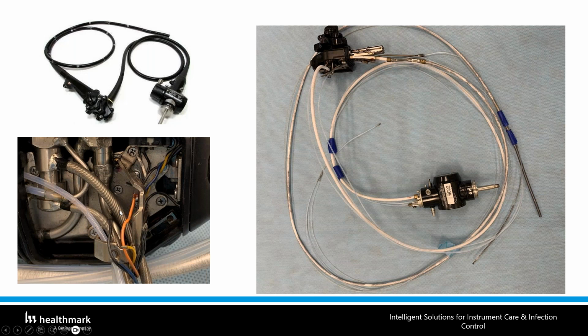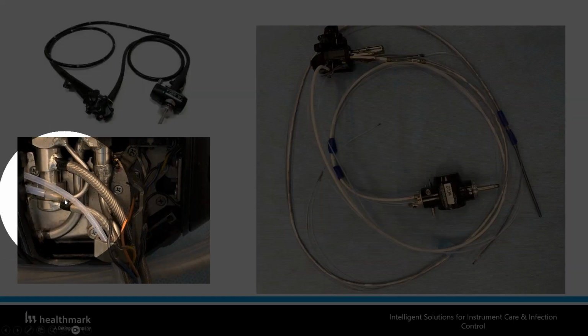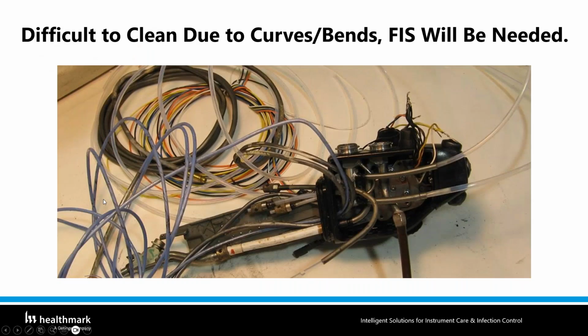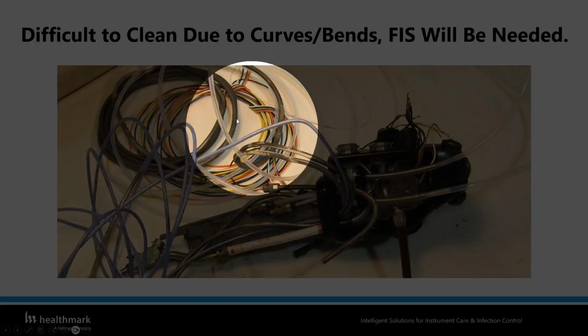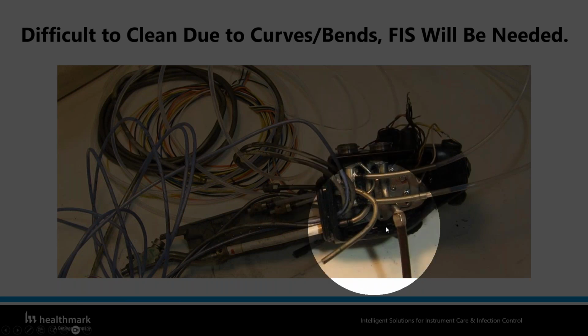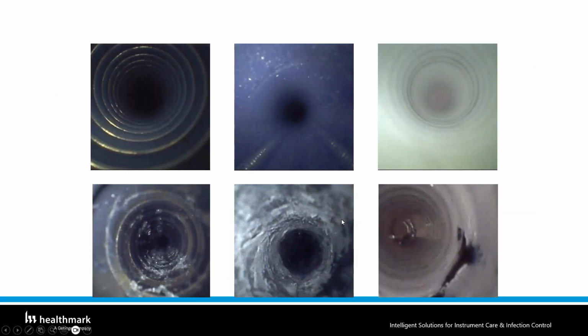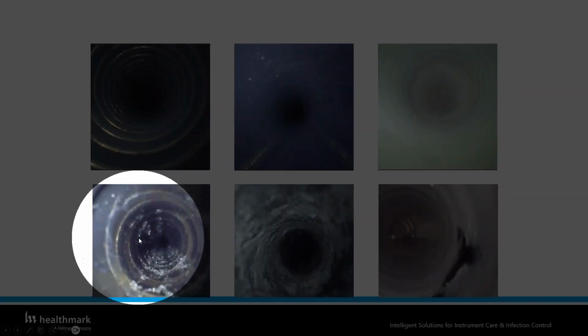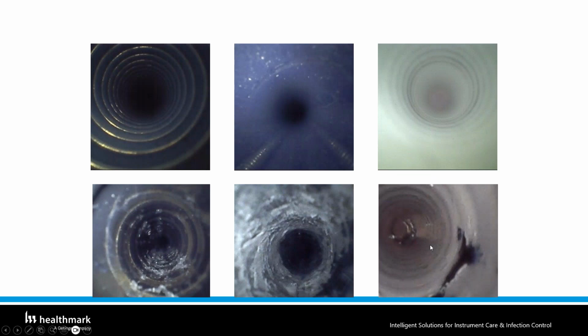So it's a nice technology, versus having to do open surgery to look inside. This does help a lot. But as you see, it is not an easy device to clean. And when you look at a slightly older one, you see that it starts getting damaged, and it's difficult to send a brush in because you have all these angles, which makes the brushing difficult. So for example, here on the top you see a nice, clean, new endoscope, and there's no issue with it. But at the bottom, in a similar area, you see that there are a lot of issues with this endoscope.